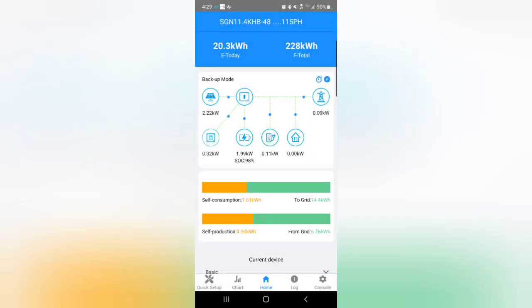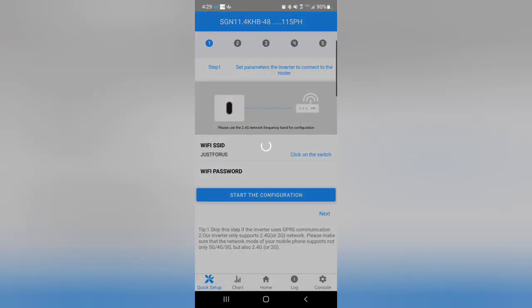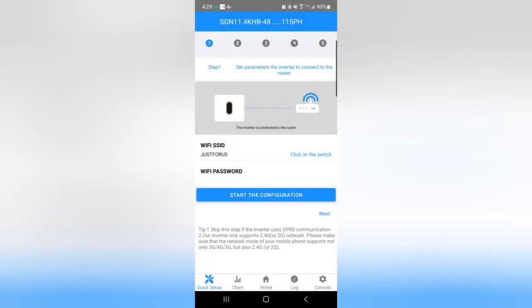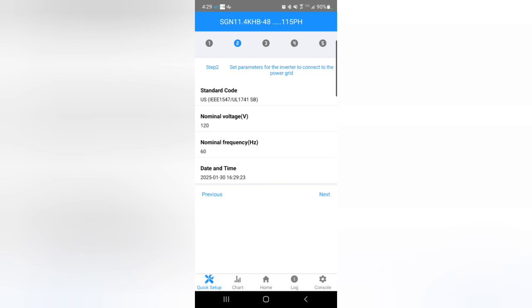That'll show you the power that's going. When you first start up, you want to go through the quick setup and connect to your Wi-Fi, making sure those Wi-Fi modules are connected, and do all your parameters. Also, on a side note, when you connect these, if you have parallel units, you can only do one at a time, so you have to put them in single mode and connect to Wi-Fi, then put the other one in single mode and connect to Wi-Fi, and then go back to parallel mode.